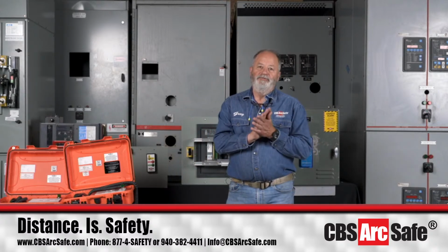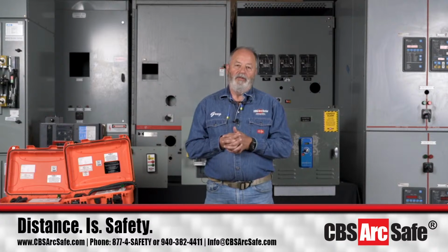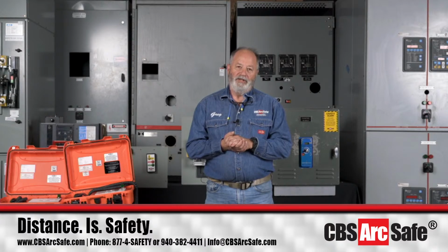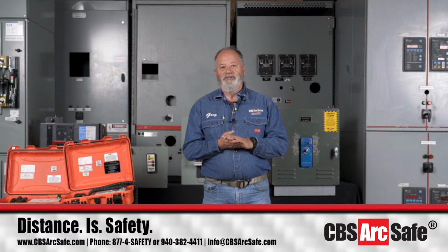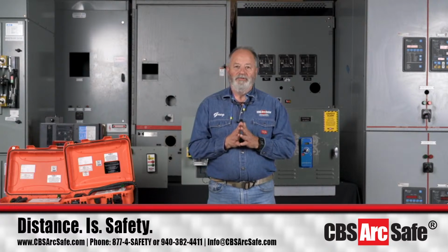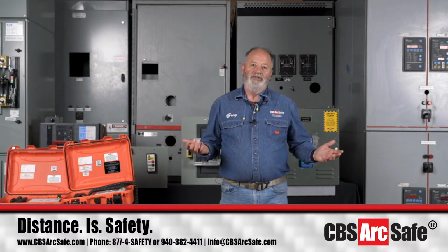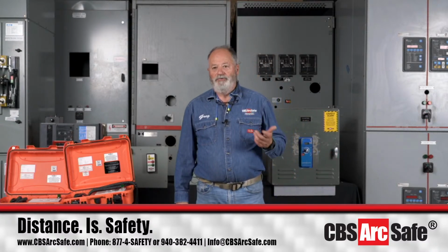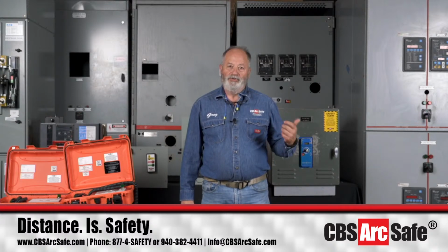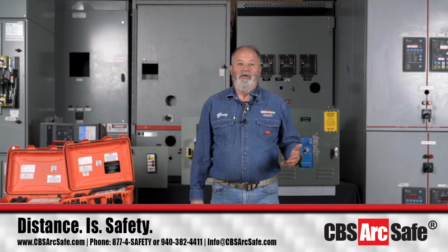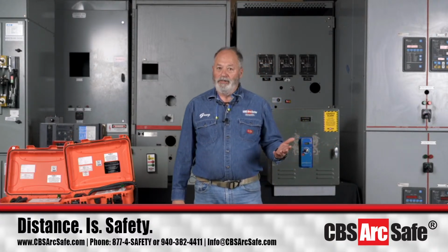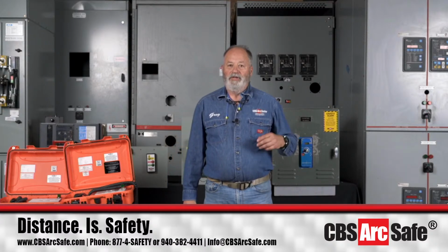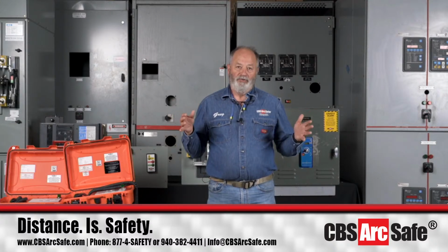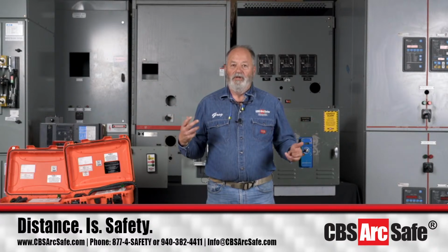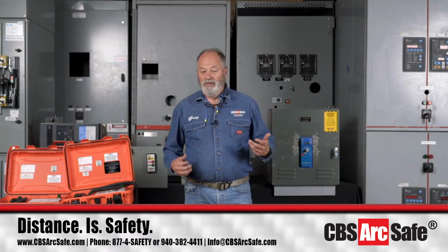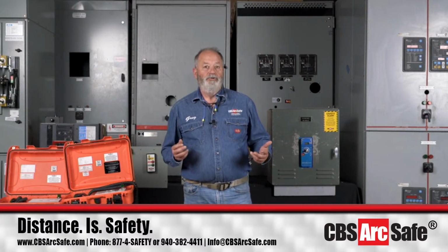I'll tell you about my first visit to a wastewater treatment plant here in Dallas, Texas, back in 2010. One of the technicians there said we always have a problem with our control switches. I talked to other parts of Group CBS, and they said you get a lot of sulfur reactions in a wastewater treatment facility, getting sulfur deposits that react with the silver or other contacts in your switches. That's the reason you have a breakdown in SCADA type gear, and a lot of times you may have to go to the face of a breaker to actually open it, versus operating from a control room, because you don't always have an air-conditioned room free of the sulfur vapors around a plant like that. You're dealing with a lot of humidity, and this causes corrosion on your switch gear that requires maintenance.